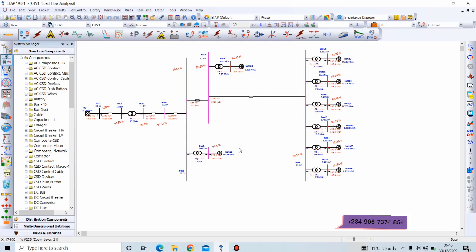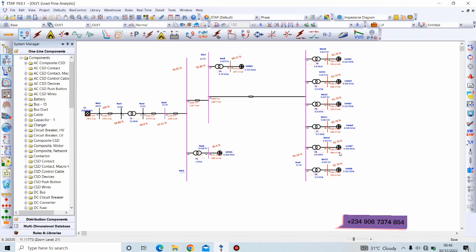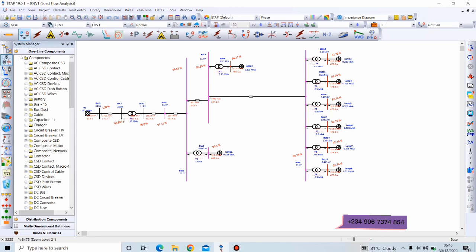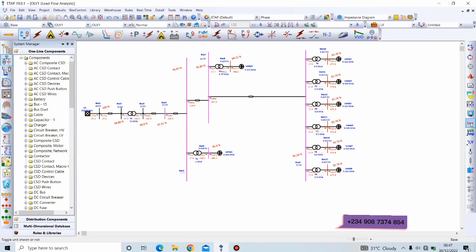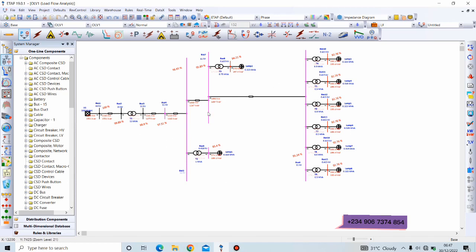That's for the bus voltages. We can also see the active and reactive power flow flowing through each bus bar. This is 2245 kilowatts and 1521 kVAR. We can choose the units we want—we can change it to amps and apparent power. Now we can see the apparent power. If yours is not showing the kVA and amps, all you need to do is come to this unit and toggle this—this removes the unit and this inputs the unit. Switching back to kilowatts and kVAR, we can see the active and reactive power flow through this.